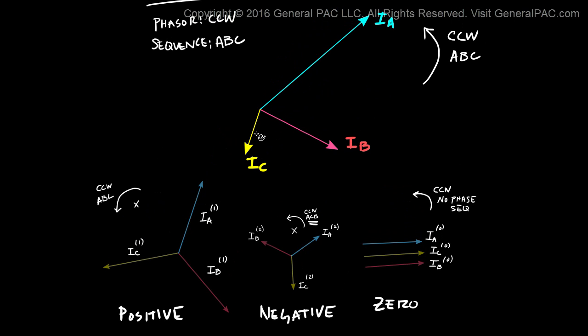Let's back up and recap. We have this unbalanced set of phasors rotating counterclockwise in an A, B, C phase sequence system. Our Positive Sequence Component is also rotating counterclockwise with a phase sequence of A, B, C — the same as our system. The Negative Sequence Component is rotating counterclockwise, but its phase sequence is A, C, B — the opposite of our system. And the Zero Sequence Component is also rotating counterclockwise, but it has no phase sequence.